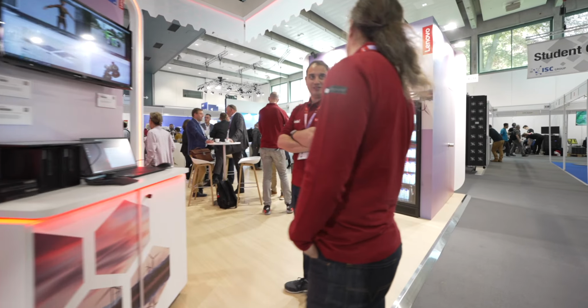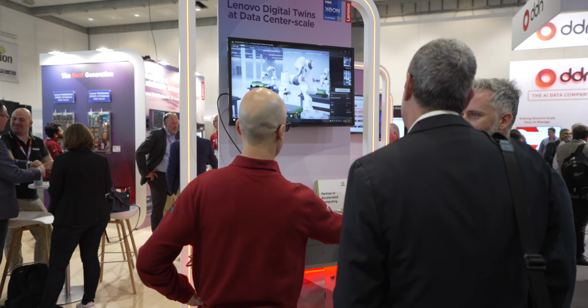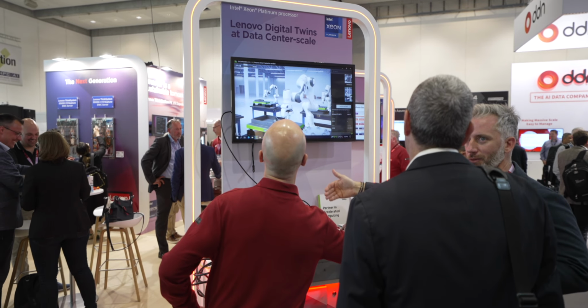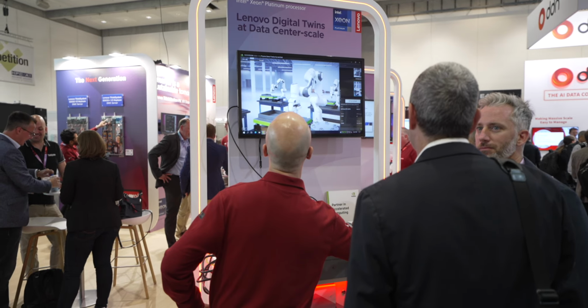We are the company in HPC with the most experience in cooling technologies, water cooling technologies. The second thing is we decided already 10 years ago to use water internally in our secondary loop, the cooling loop behind the CDU. That's the cooling loop we build with the customer, deploy with the customer, install for the customer - we do the plumbing and piping as part of the engagement. We don't leave it to a third party. We have specialists in our professional services team who do the CDU installation, the plumbing and piping under the floor, connect to the primary water loop, and everything needed from a plumbing, piping and connectivity perspective.